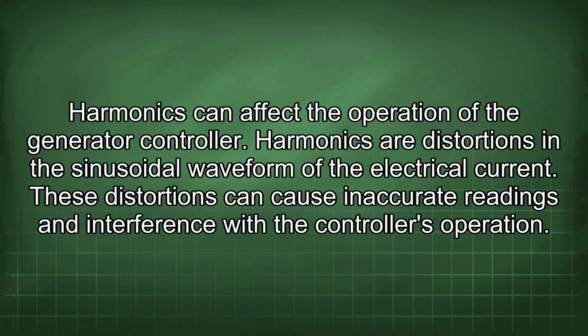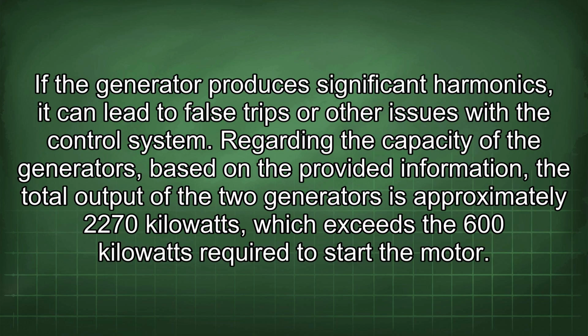Harmonics can affect the operation of the generator controller. Harmonics are distortions in the sinusoidal waveform of the electrical current. These distortions can cause inaccurate readings and interference with the controller's operation. If the generator produces significant harmonics, it can lead to false trips or other issues with the control system.